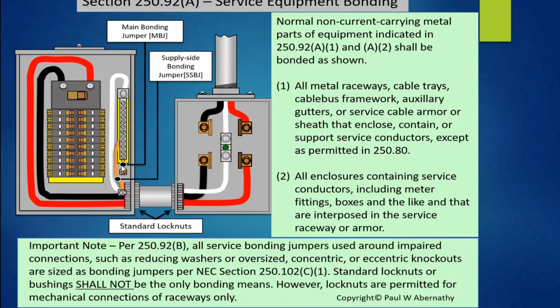Now, if this is a main bonding jumper, if it's factory installed, like a strap, or it was a green screw in here, again, we don't do anything. If it is of the wire type, we're going to size it as well based on the size of these service entrance conductors that are supplying it. All of that ties everything together. Now, we're also going to get into what happens if these knockouts were impaired or oversized, concentric or eccentric, or reducing washers were used, or there's some kind of damage. We're going to cover that in a second. In this one, we'll say that's probably a concentric knockout, so he used a bonding jumper here. Because if you encounter reducing washers, oversized, concentric, or eccentric knockouts, or any impaired connection, then you're required to use a bonding jumper.